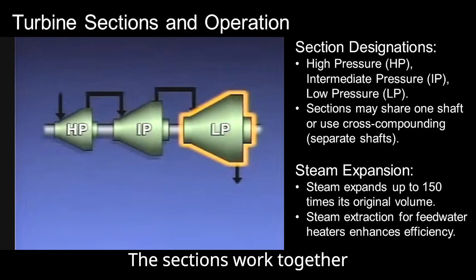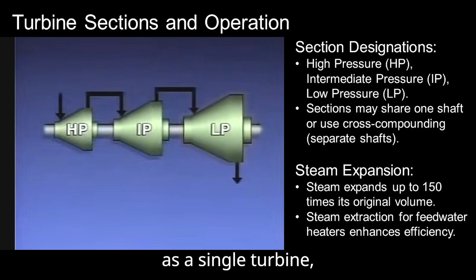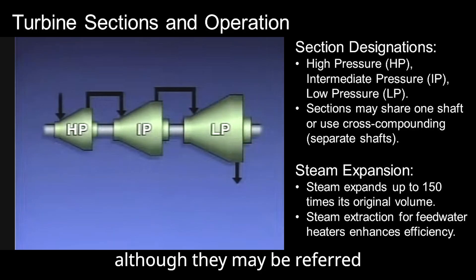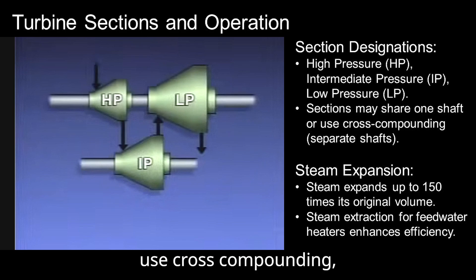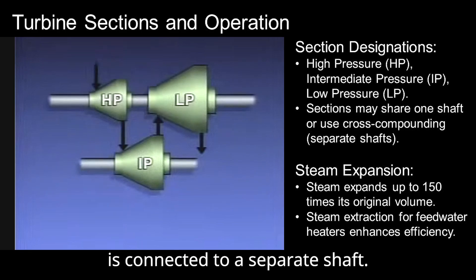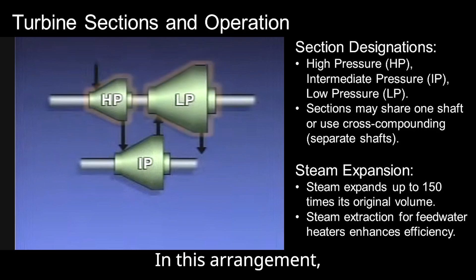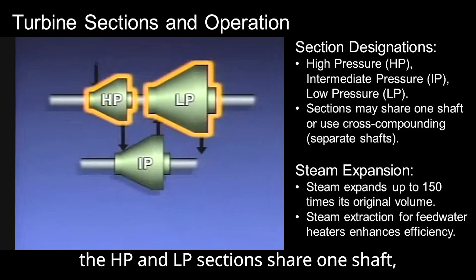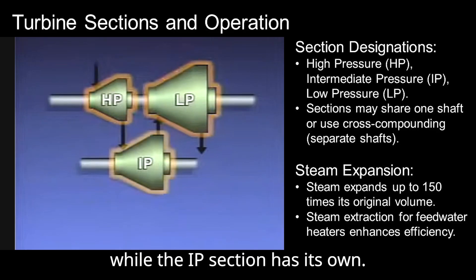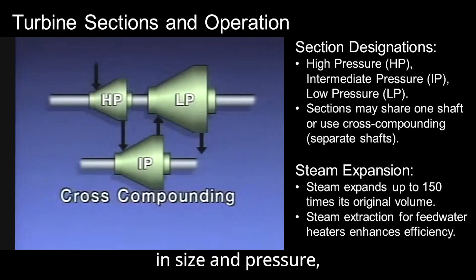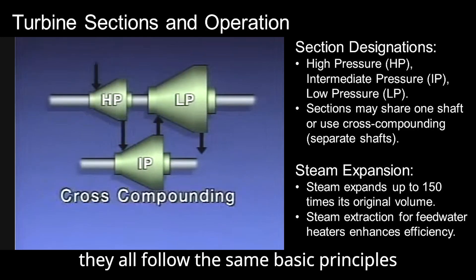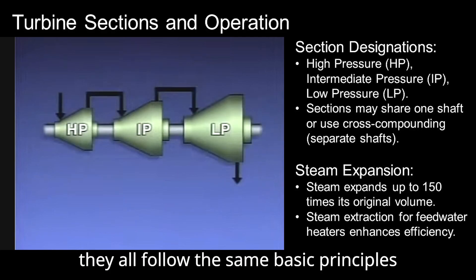The sections work together as a single turbine, although they may be referred to individually. Some turbine designs use cross-compounding, where each section is connected to a separate shaft. In this arrangement, the HP and LP sections share one shaft, while the IP section has its own. Although the sections differ in size and pressure, they all follow the same basic principles of operation.